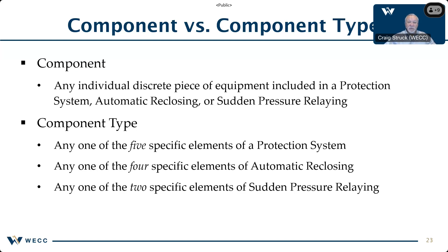Thank you, Craig. So I'm going to jump in and provide the applicable facilities for PRC 5-6, and this first one is protection systems. A protection system includes protective relays, associated communication systems, voltage and current sensing devices, station batteries, and DC control circuitry. Applicable protection systems include systems installed for the purpose of detecting a fault on the bulk electric system, also known as the BES, such as lines, buses, transformers, etc.